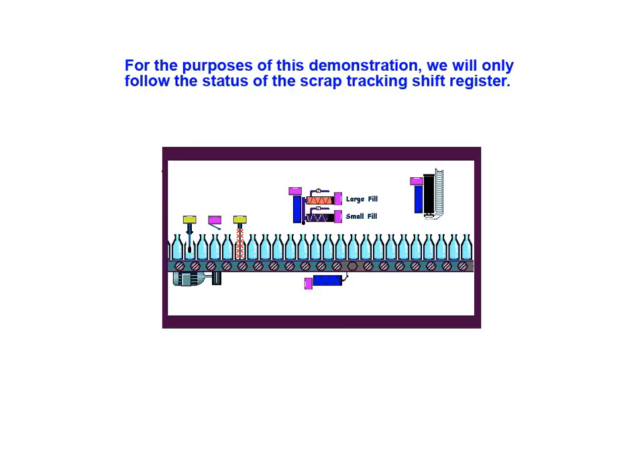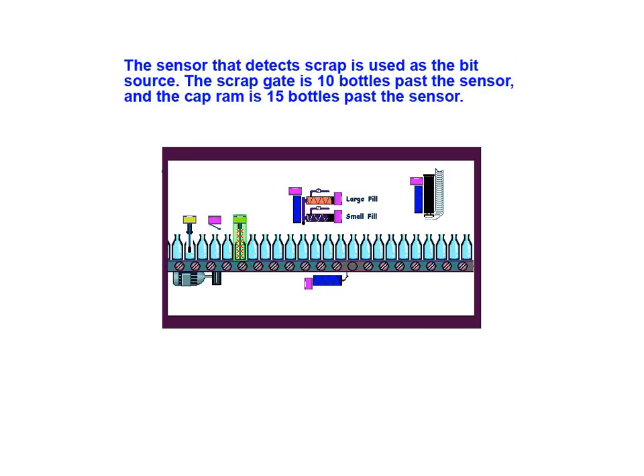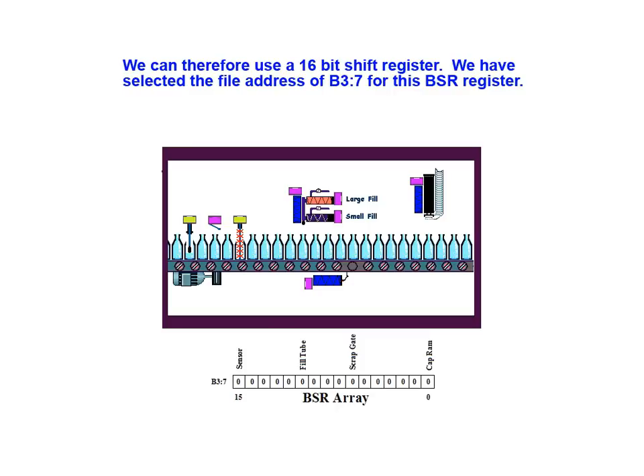For the purposes of this demonstration, we will only follow the status of the scrap tracking shift register. The sensor that detects scrap is used as the bit source. The scrap gate is 10 bottles past this sensor, and the cap ram is 15 bottles past this sensor. We can therefore use a 16-bit shift register.